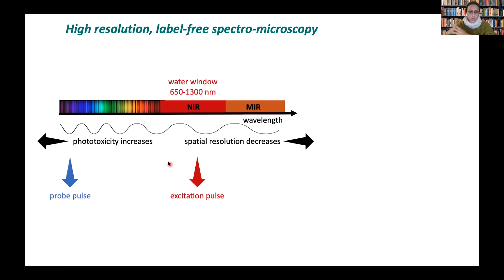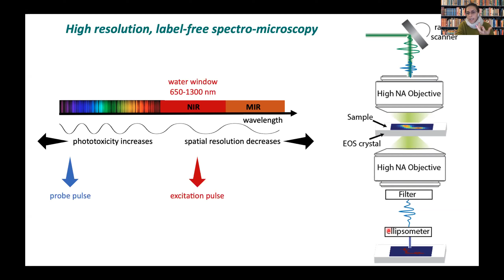And then if you just couple these two lights to your objective, and put your sample in contact with the nonlinear medium that you have to generate this response, then you can do point-by-point measurements, get spectroscopic information and make an image. So this is the setup that we aim to build at NPL at the moment. But of course, we needed some proof of principle measurement to make sure that we can really nicely detect this molecular response, or whether our device is sensitive enough.